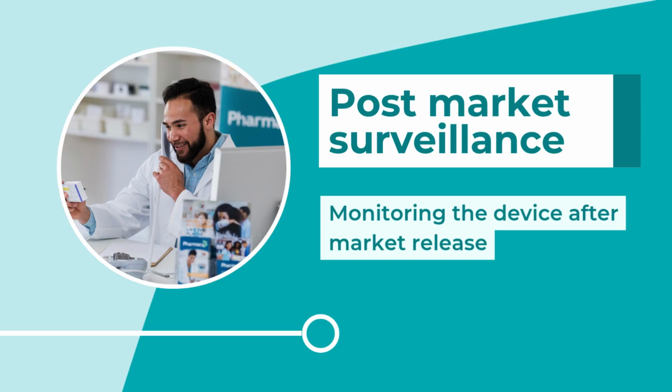All post-market findings feed back into clinical evaluation and risk management documents, closing the loop and starting the cycle again. In summary, MDR compliance is a continuous loop. Classify the device, secure certification, monitor performance, update the documentation, and then repeat for as long as the product remains on the EU market.